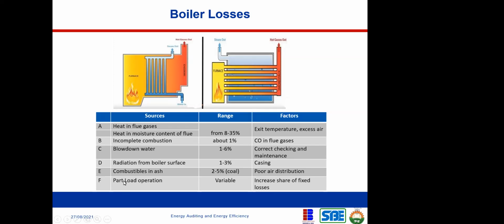That's what it means. So another source of heat loss is part load operation. Of course, we know that when you're operating any appliances or any equipment at part load, it is not at best efficiency. It's not the best efficiency practice. Okay, so the same thing is applicable to the boiler. When you're operating a boiler at a part load, you're not operating at the best efficiency level.